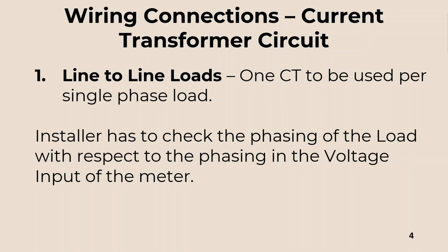Before configuring the meter, it is very important to know how to wire and install the current transformers. In two-wire single-phase loads, there are two ways to connect the loads. One is the line-to-line loads. In the Acuvim single-channel meters, you need one CT for each load. The installer has to check the phasing of the load with respect to the phasing of the voltage input of the meter.